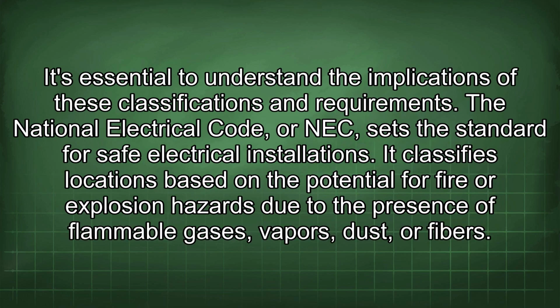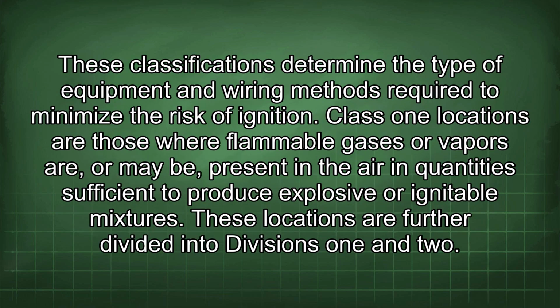It's essential to understand the implications of these classifications and requirements. The National Electrical Code, or NEC, sets the standard for safe electrical installations. It classifies locations based on the potential for fire or explosion hazards due to the presence of flammable gases, vapors, dust, or fibers. These classifications determine the type of equipment and wiring methods required to minimize the risk of ignition.